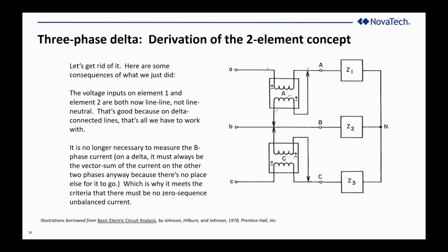Why do I have to measure 3 currents if the third current must, with no exceptions, be the vector sum of the other 2 currents? So the concept that I can measure the total watts of a delta-connected 3-phase load without any concern over the B-phase current is not counterintuitive when you consider that you're measuring the A-phase current and the C-phase current, and the B-phase current has to be the sum of the other 2. And this is really the underlying key to the proof that we were talking about before, that there's no place else for the current to go.